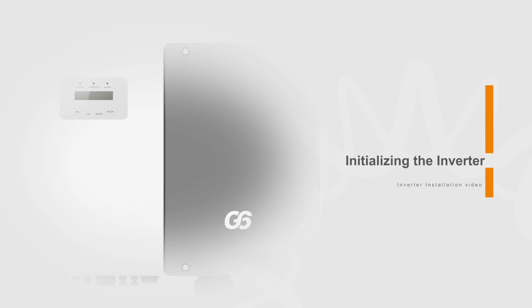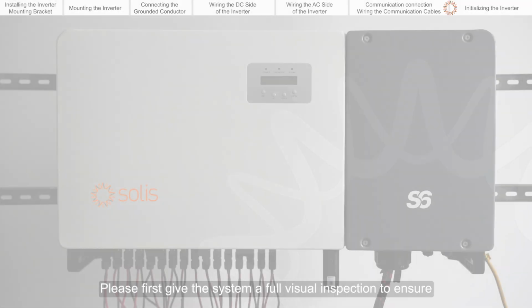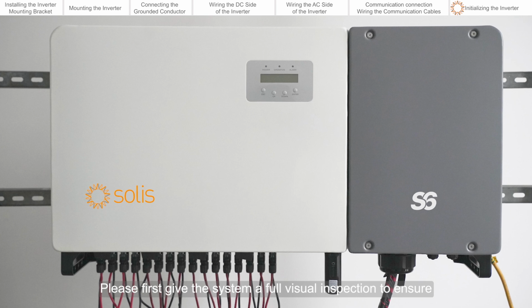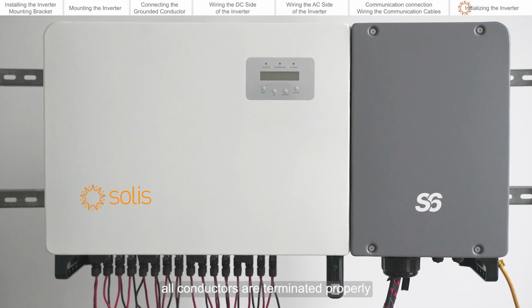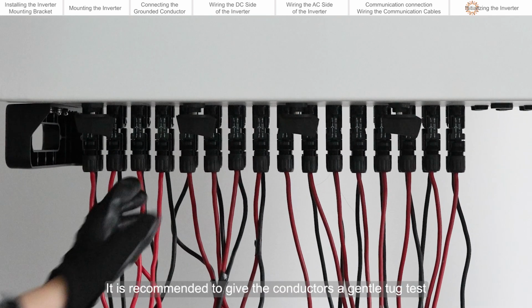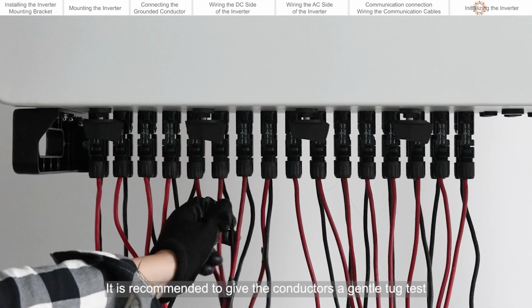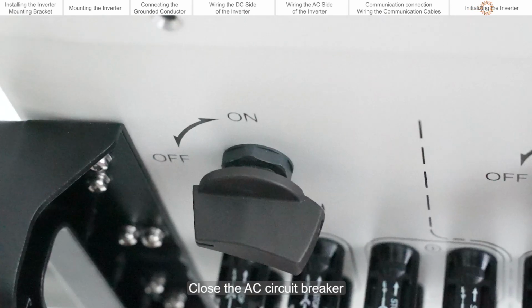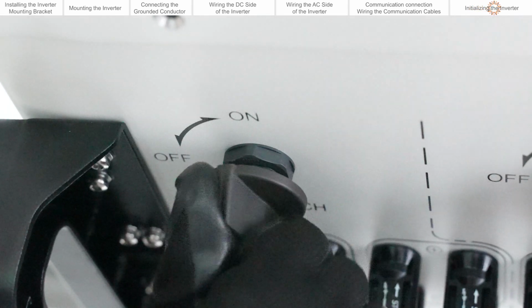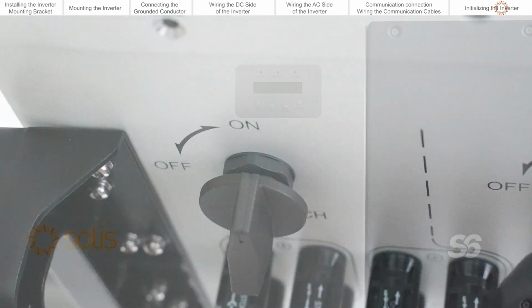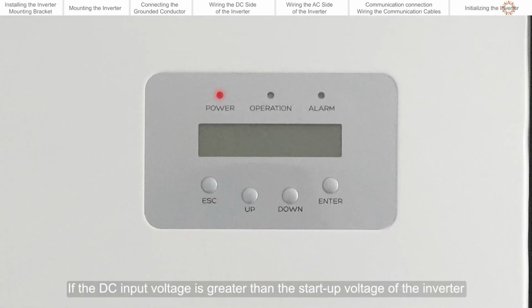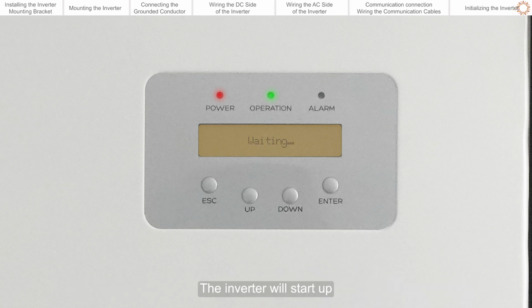Initializing the inverter. Please first give the system a full visual inspection to ensure all conductors are terminated properly. It is recommended to give the conductors a gentle tug test. Close the AC circuit breaker. Close the DC switches. If the DC input voltage is greater than the startup voltage, the inverter will start up.